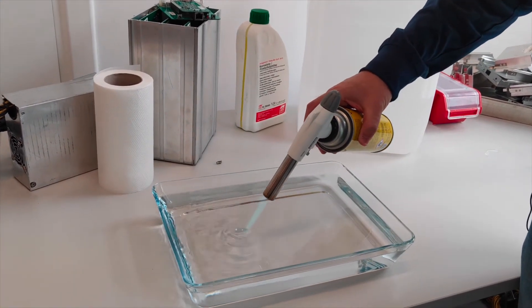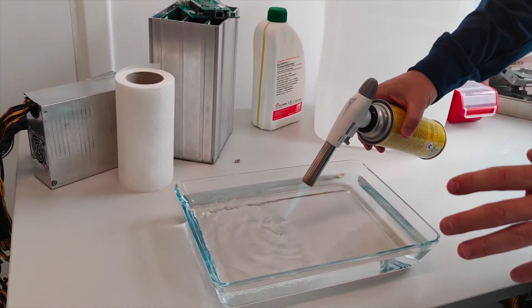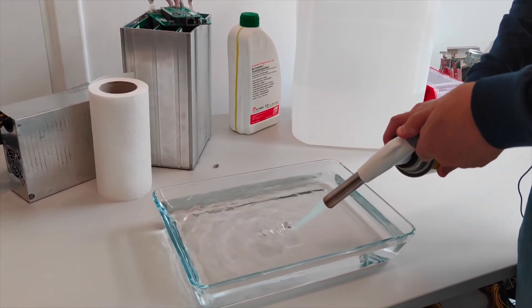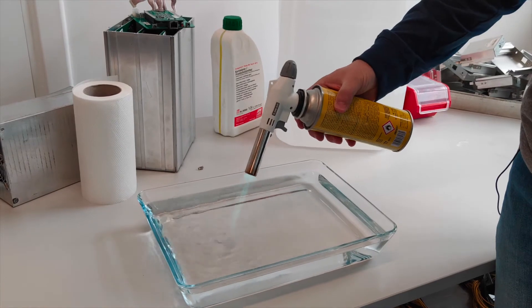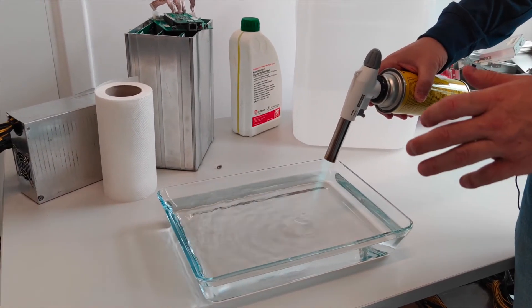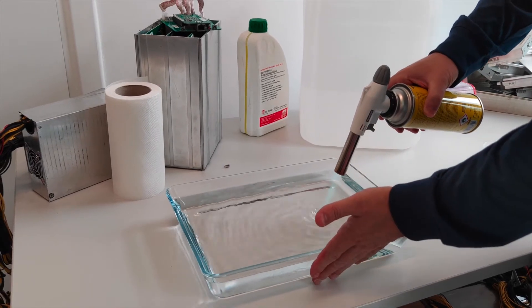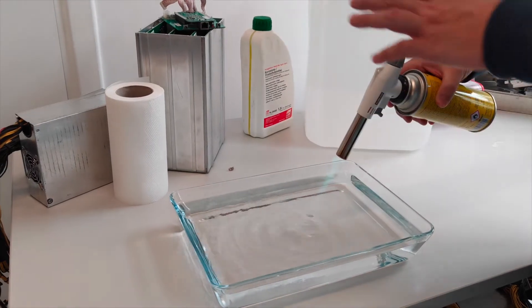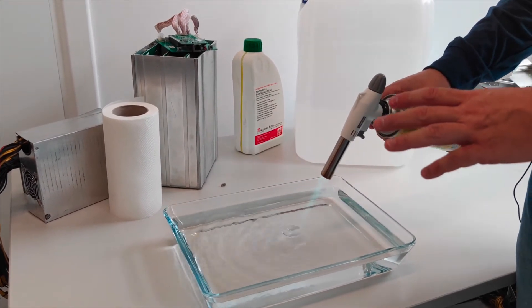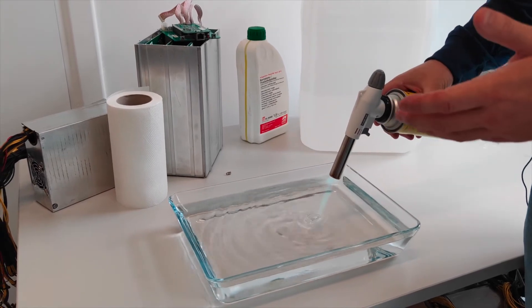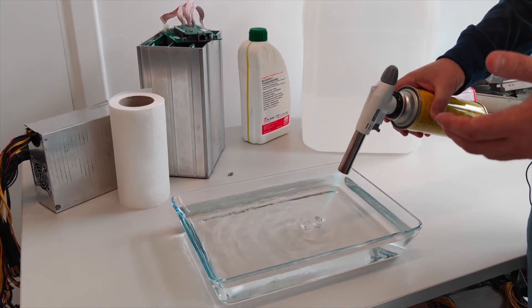Some people demonstrate it using lab coats or other methods to make it more fancy, but we will not make it really fancy. The thing is, you cannot, you need to reach certain temperature of the whole immersion cooling system to be able to reach the combustion point or fire point. So the fire point of that fluid is over 160 Celsius.